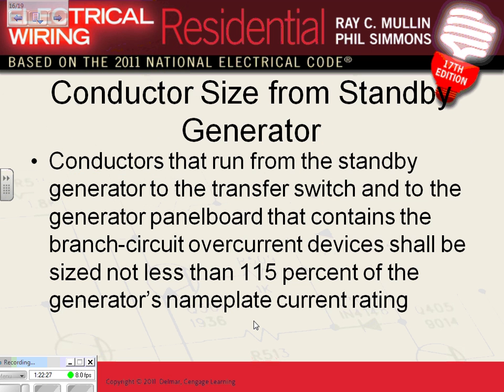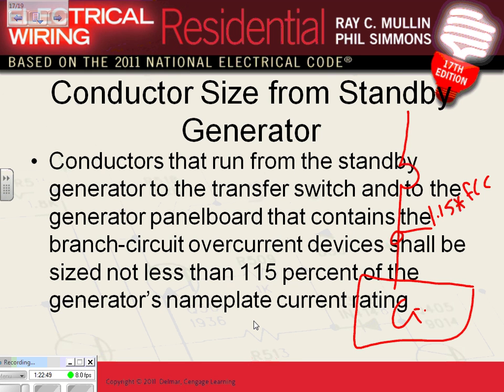So, all right, generator runs standby. When we size generators, and I don't want to open this can of worms, guys, but I'm going to remind you of one other thing. When we size generators, for the conductor we take 1.15 times the full load current of the generator. If this is my gen, here's my gen. I'm not going to open this can of worms for one reason, because I open it next quarter. We size the generator conductors by 115. Why 115, not 125? Because the code, Article 445, says 115.